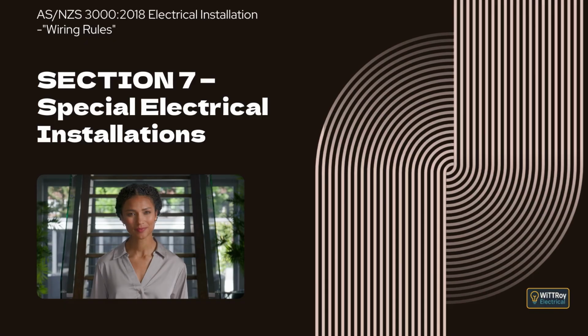Clause 7.5.11.3 Underground conductors. This clause explains that there are no specific burial depth requirements for extra-low voltage cables from a safety perspective, but careful consideration must be given to the risk of mechanical damage. Clause 7.5.12 Testing. This clause introduces the testing requirements that confirm the separation and safety of extra-low voltage circuits.